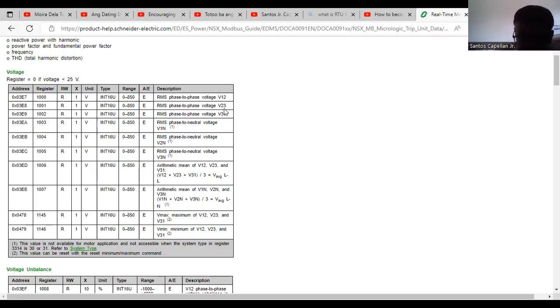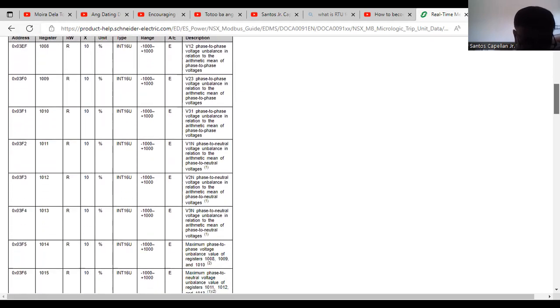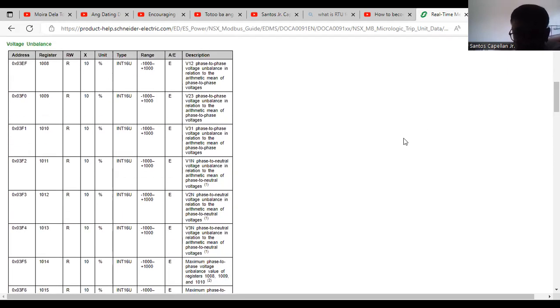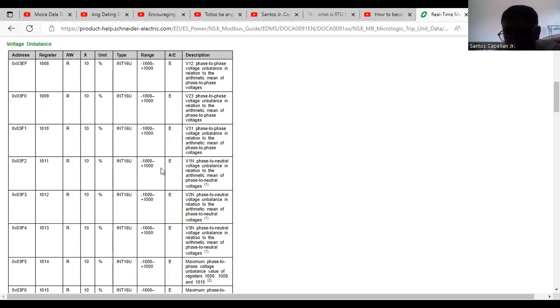You can also display phase-to-neutral voltage and RMS current — for example register 1016 for current on phase 1. It depends on the specification: what are the important points to be displayed? You don't need to display all information — maybe just phase-to-phase voltage, current drawn from each phase, and power factor. You don't need to create excessive traffic in your BMS network.